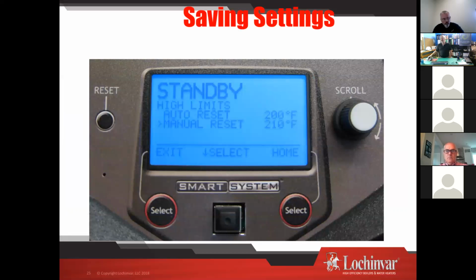All right, let's talk a little bit about auto and manual reset high limits. My recommendation is leave them alone. Every once in a while, people change them. You really don't need to. Remember, you have a low mass boiler, so there will be drifting temperatures. You could get some extra energy sometimes dumped into the tank temperature within the heat exchanger. So if I said, boy, 210 makes me nervous, 200 makes me nervous, I'm going to set it to 190, and you're running your boiler at 180, which will let it go to 185. If it shuts off at that temperature, you could see a little bit of stack from that 185 to maybe 190 and trigger a high limit reset. So keep those up and out of the way.